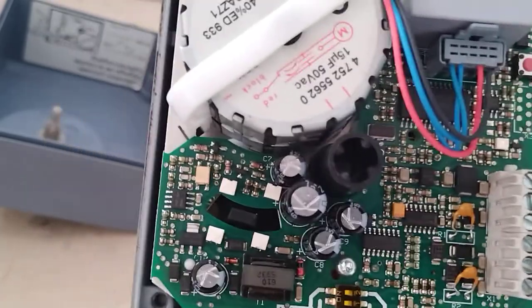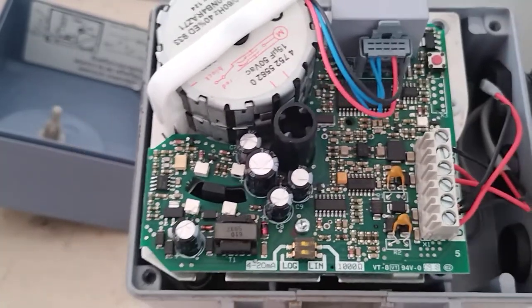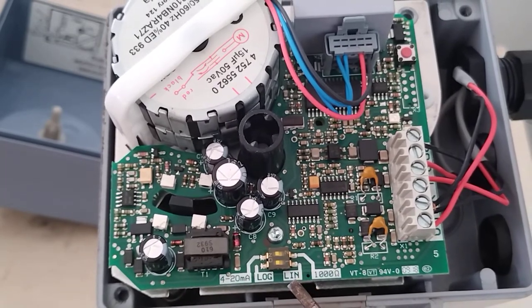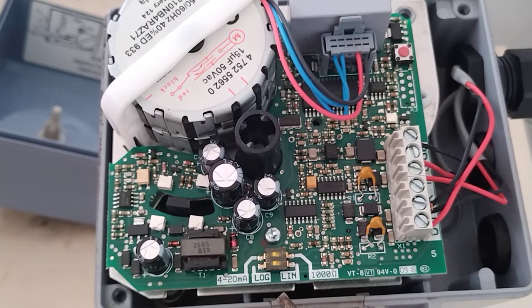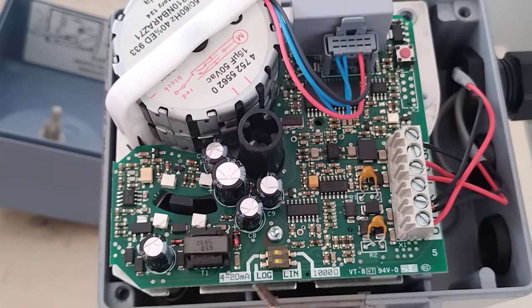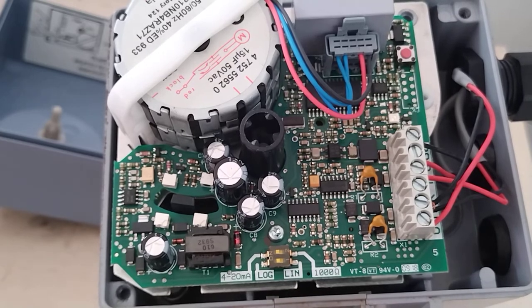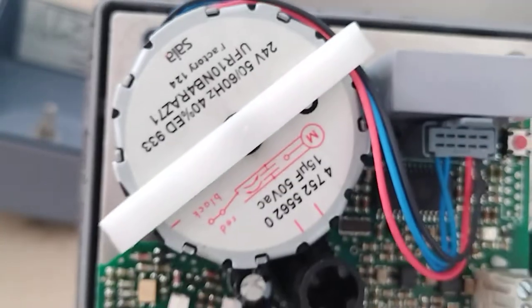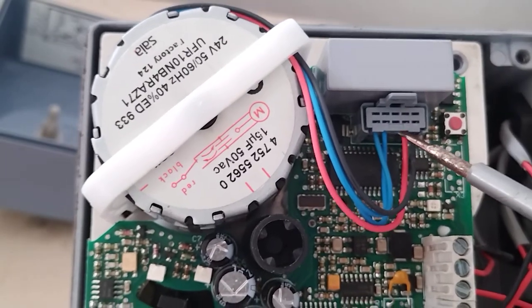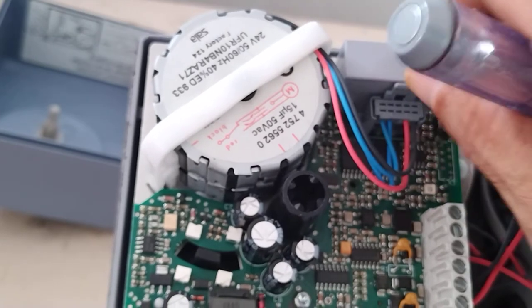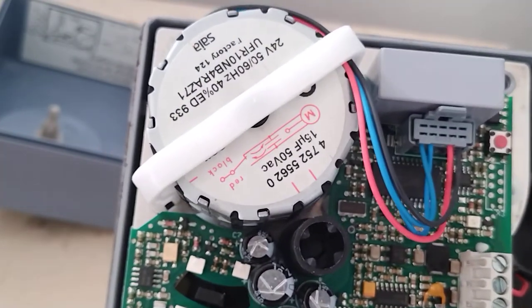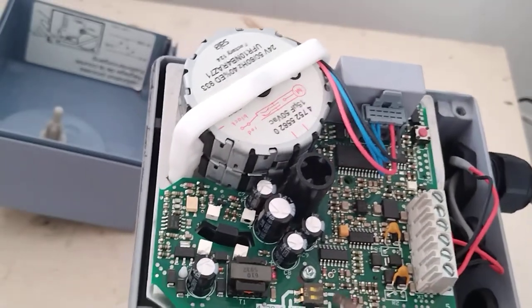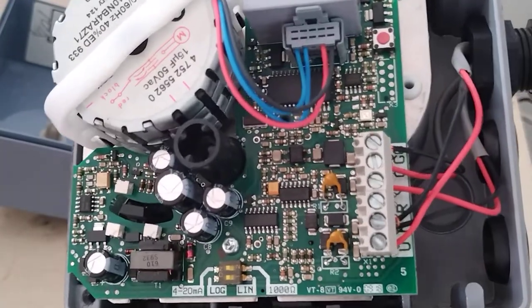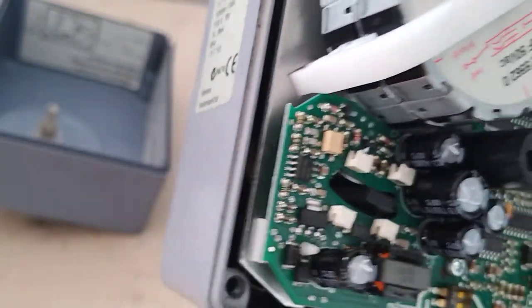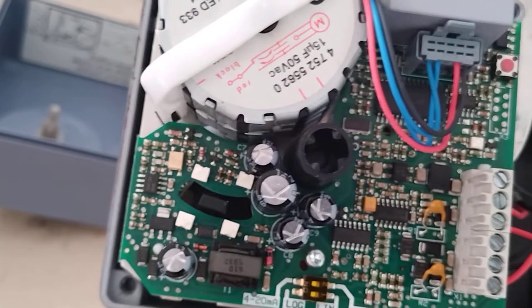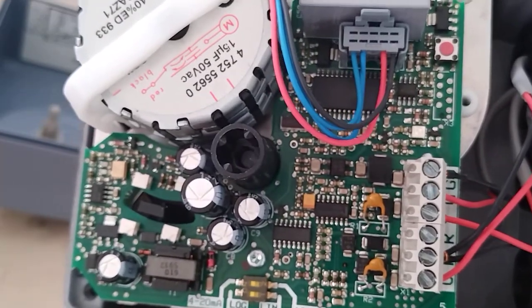So here now there will be dip switches here. It will tell you what will be the setting, but this one I set this one to 0 to 10 volts. So this will be the connection here. This is the only dip switch I can see from this one, for setting it, but I think this is already set to 0 to 10 volts. So this is our valve actuator.